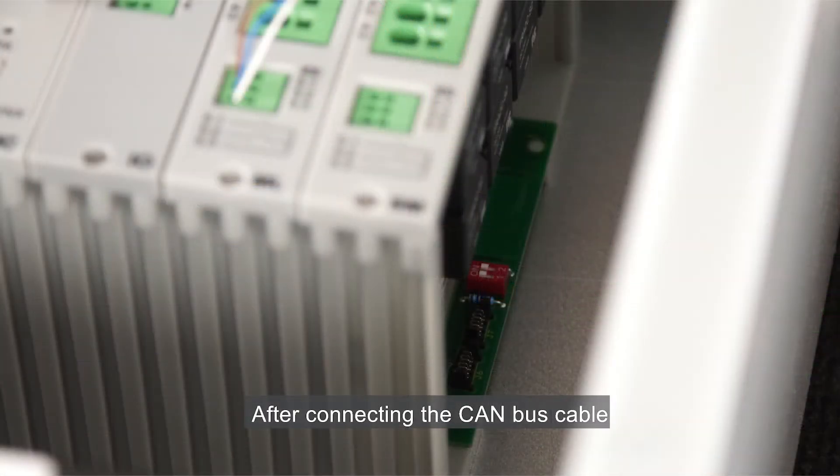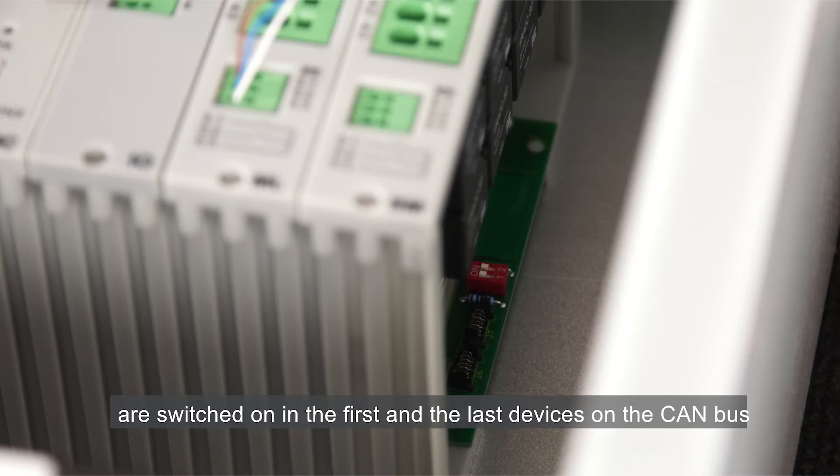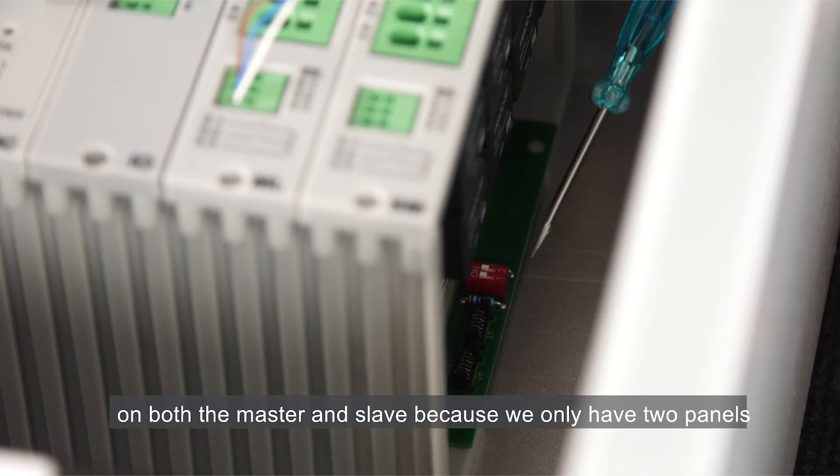After connecting the CAN bus cable, we need to make sure that micro-switches for the end cable module are switched on in the first and the last devices on the CAN bus. The switches are located here on the back plate. I've turned them on, on both the master and slave, because we only have two panels.